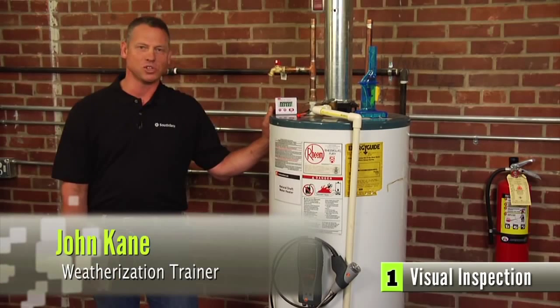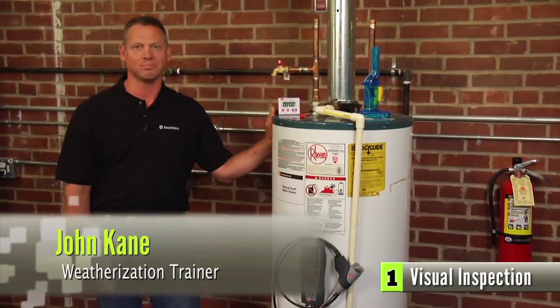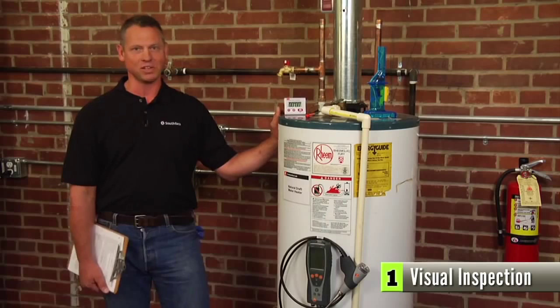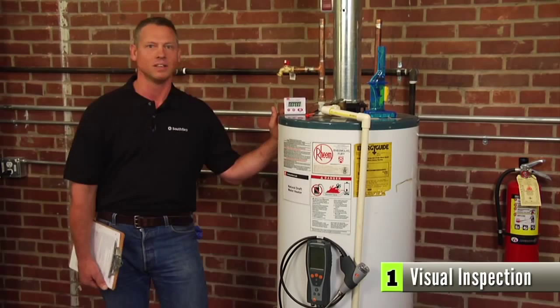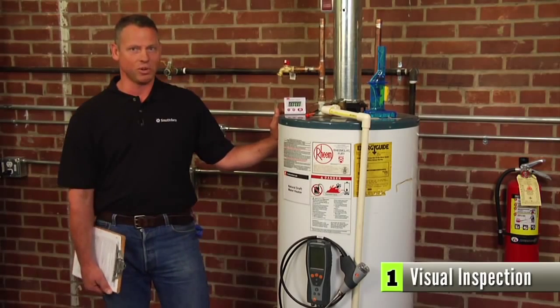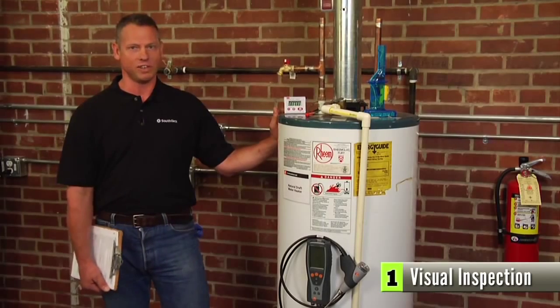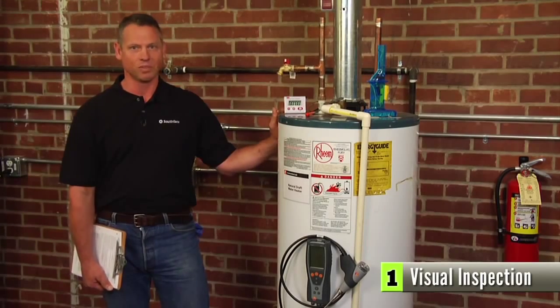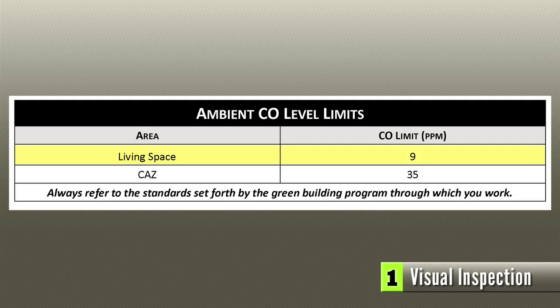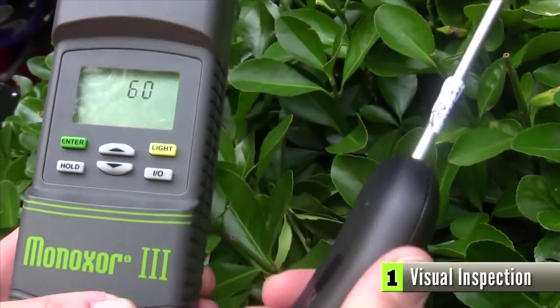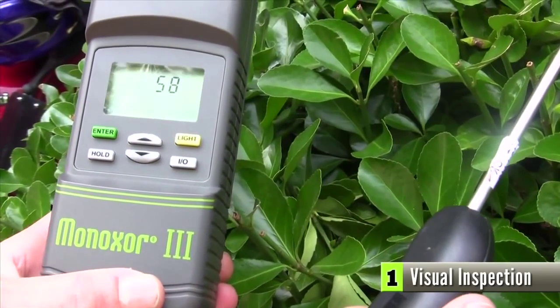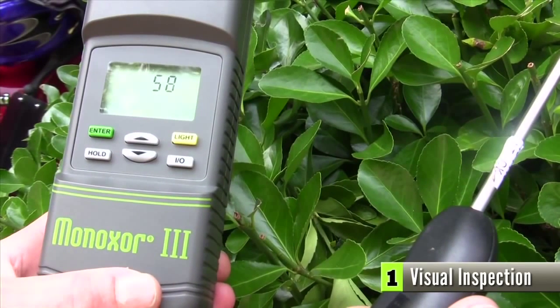The first part of combustion safety testing is a visual inspection. Before starting any diagnostic test, you should make sure the house conditions are safe for testing. For combustion safety testing, you want to conduct a thorough visual inspection of each combustion appliance that will be tested. Your visual inspection should also include monitoring the ambient carbon monoxide levels in the home and the combustion appliance zone. So before entering the home, you want to turn on your CO monitor and have it with you as you walk through the house conducting your visual inspection.